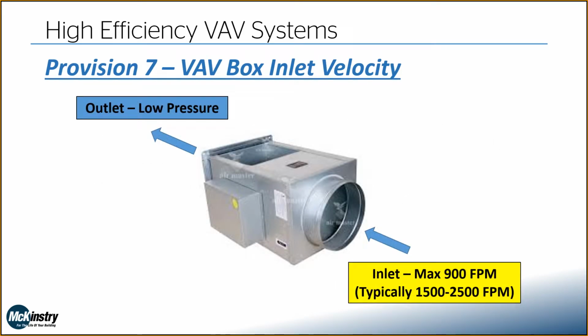So just to visualize it, here's the typical VAV box. On the inlet, we're saying it can't have more than 900 feet per minute. Typically, you'd be in the range of 1,500 to 2,500 on a standard VAV box design.